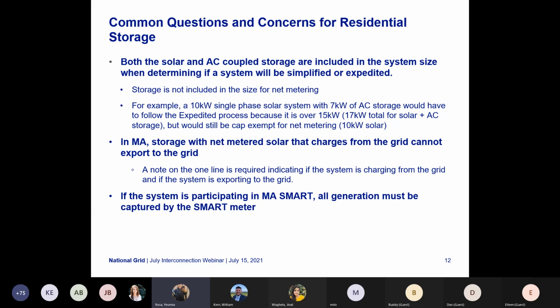For example, a 10 kW single phase solar system with 7 kW of AC storage would follow the expedited process because it is over 15 kW on a single phase. However, the net metering is capped at the 10 kW. In Mass, the storage with net metering solar that charges from the grid cannot export to the grid. So it's important that your one line does mention how the system is charging and if it is exporting to the grid. That is something that we look for on the one line when we do the review. So that is important to include on that one line, a little note somewhere.